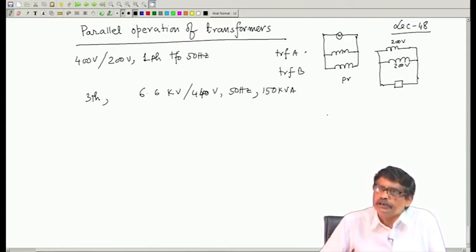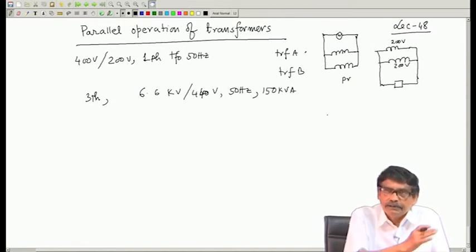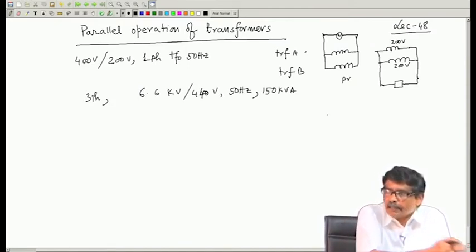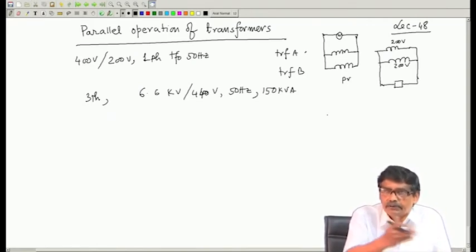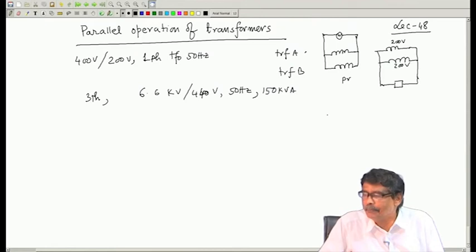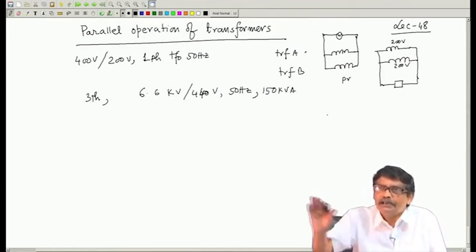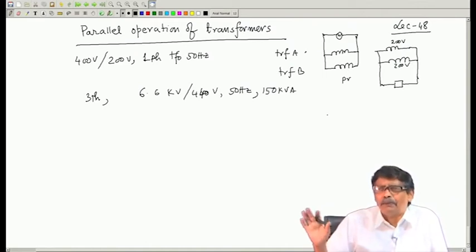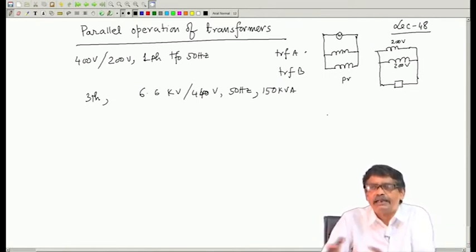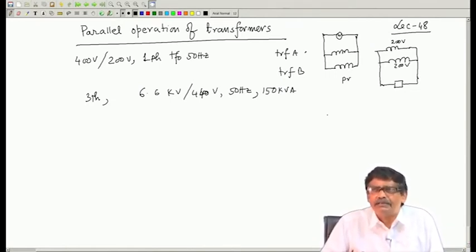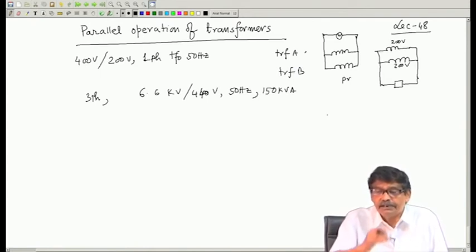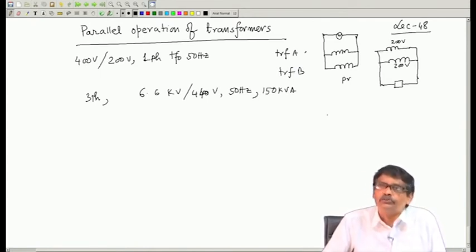The cost of each unit is small. In fact, if two or more transformers are operating in parallel, you can keep one transformer ready, I mean not in use, as a backup. So, if one transformer is faulty, temporarily power will be interrupted to some consumers, but you connect that new one and take the faulty one for servicing. That is the whole idea, very simple logic, nothing great. But that is why operating transformers in parallel assumes importance. Okay.